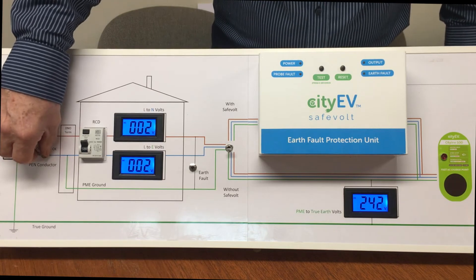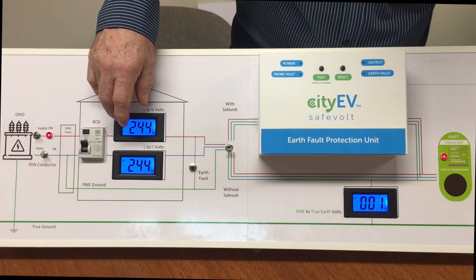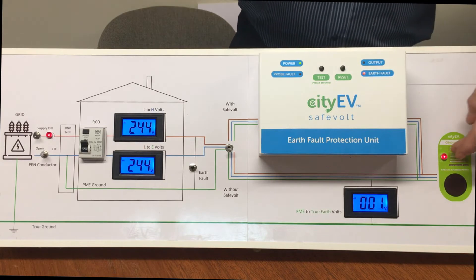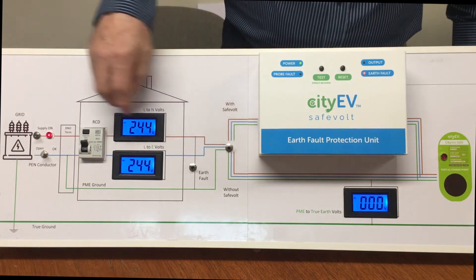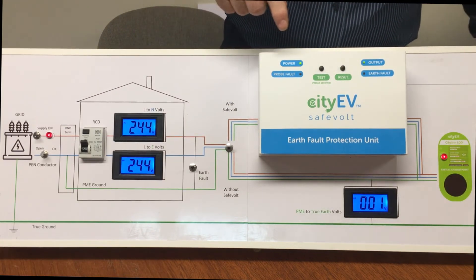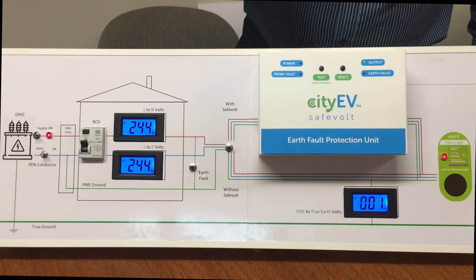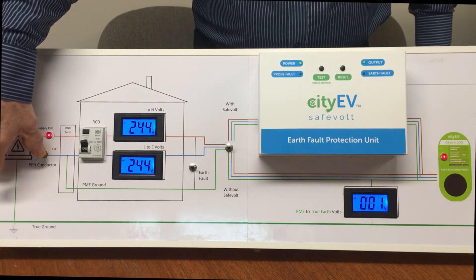We reconnect the PEN conductor: voltage to the installation returns to normal, voltage between PME earth and true earth reverts to zero, and the charge point is powered back on. This time, we route the supply through the Safevolt to the charge point. The charge point is powered up through the Safevolt, all is normal, and ground voltage is zero. We then introduce a PEN conductor fault again.